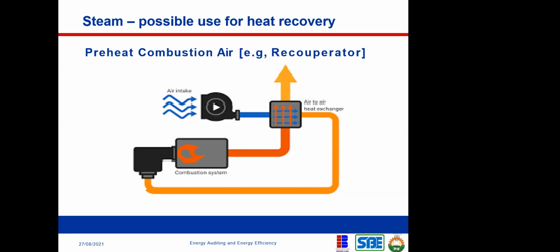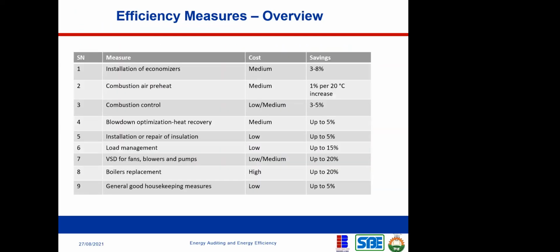So you now inject that air into your combustion chamber. Now this is your combustion chamber. You inject the air into your combustion chamber. Now, because that air is coming into your combustion chamber hot already, right? It's going to improve the combustion efficiency of your boiler. So that's what the combustion air preheat means. So you can also do combustion control, okay, in terms of your excess air, how much excess air you add into your combustion and all of that. You can do that. Then blow down optimization heat recovery.